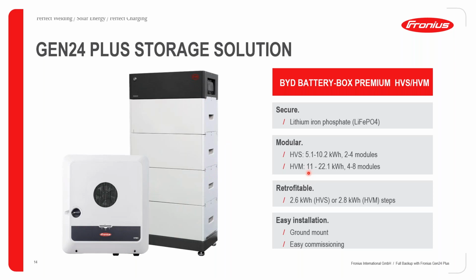We also then get the HVM, which starts from 11 and goes up to 22.1 kilowatt hours, and that starts from 4 to 8 modules. Okay, so each gray module, as I said earlier with the HVS, is about 2.6 kilowatt hours, and each gray module is about 2.68 kilowatt hours for the HVM. The advantage of the BYD battery, 2 key advantages, is you can do a ground mount system, and the commissioning is, again, extremely simple.